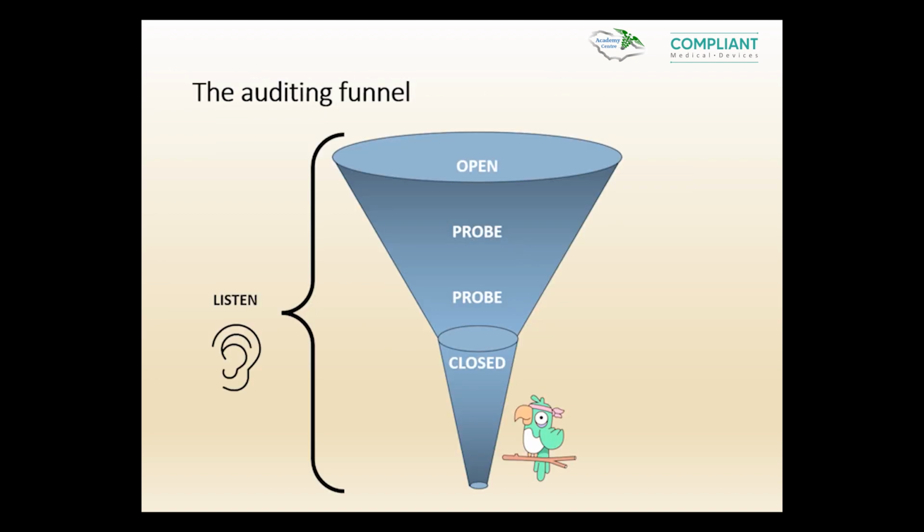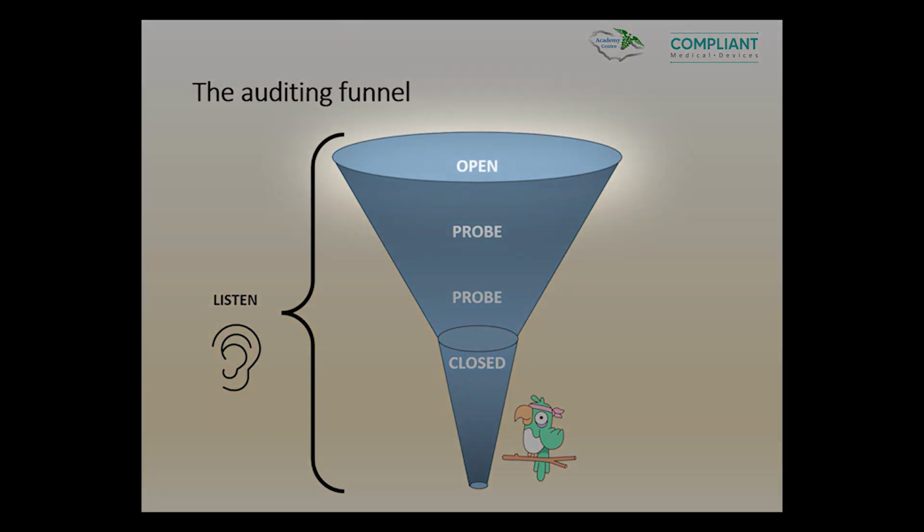13485-2016. The audit funnel itself, with respect to its methodology, begins with an open question. Open questions let the auditee get into a rhythm and a method of responding to be able to demonstrate to you their competency, knowledge, and ultimately the process compliance, which is what the auditor and the audit is trying to assess at any given time. With respect to the open question, an example of this is: tell me about your management review process.